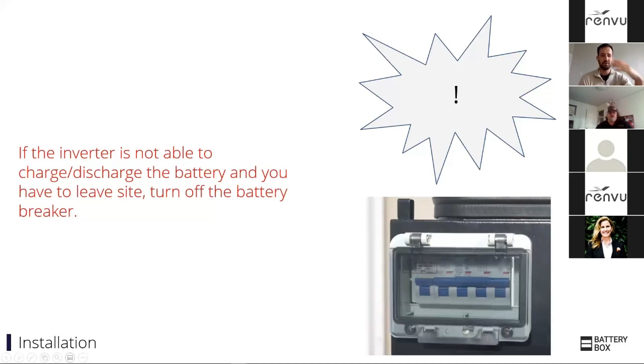As you note, you can't really check the voltage there until you're communicating with the inverter. So during that commissioning process, there's no LEDs, for example, on the outside of the BYD box. The switch itself is actually kind of easy to operate, and it's protected by that cover. So it's just best practice, when you're doing your system setup and some of your wiring, to shut her down before you get fully commissioned.